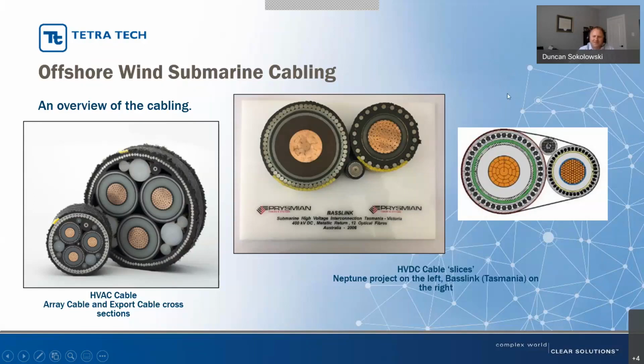So the industry standard at the moment is a bipolar system where you have a bundled cable with the power, the return, and a small third cable which has the fibers in it. These are bundled as they leave the ship and get laid in a single package of this oval shape. HVDC cables already exist in the New York Bight area - there's the Neptune project going from New Jersey to Jones Beach on Long Island, and then the cable that crosses Long Island Sound as well.